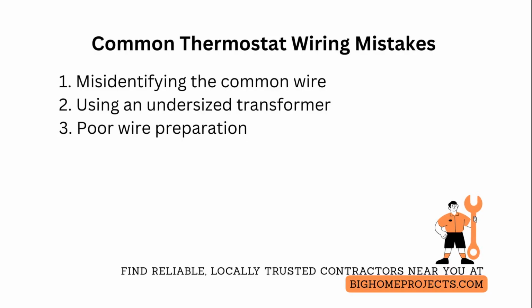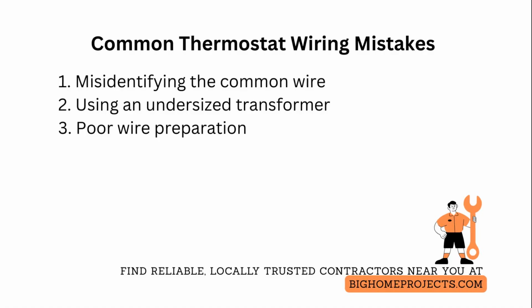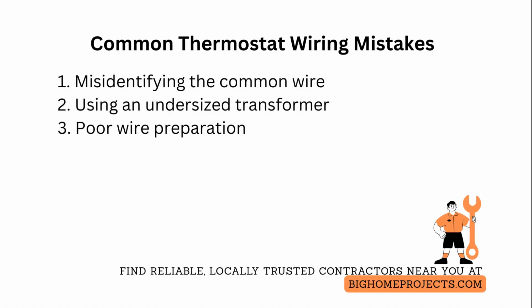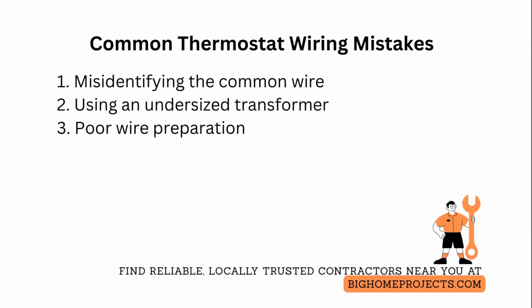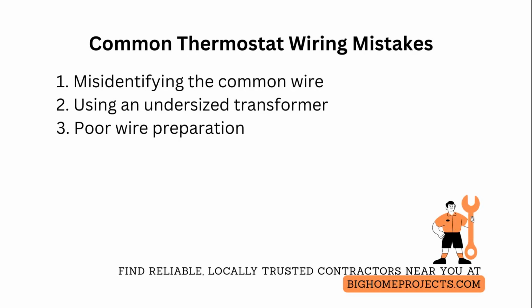One of the common problems is poor wire preparation, frayed strands or loose strands at screw terminals causing shorts or intermittent connections. Remedy that by trimming, tinning, or using ferrules on stranded conductors, firmly seating them under the terminal screw, and using strain relief clamps at both the thermostat and the control board.